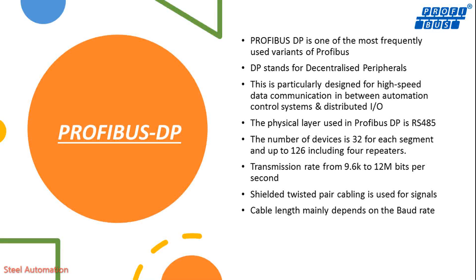The number of devices is 32 for each segment and up to 126 including four repeaters. Transmission rate ranges from 9.6 kbps to 12 Mbps. Shielded twisted pair cabling is used for signals.